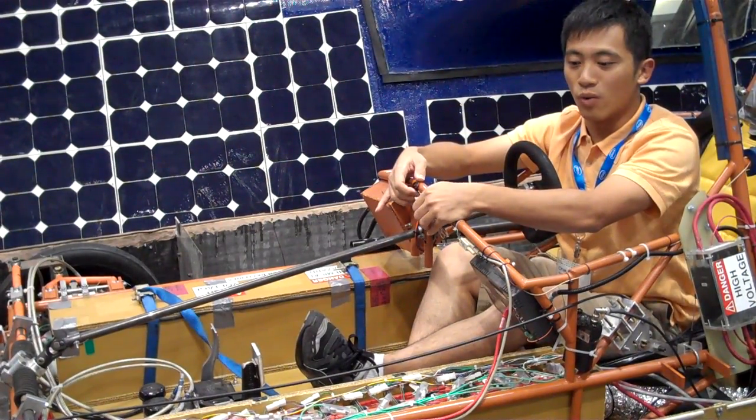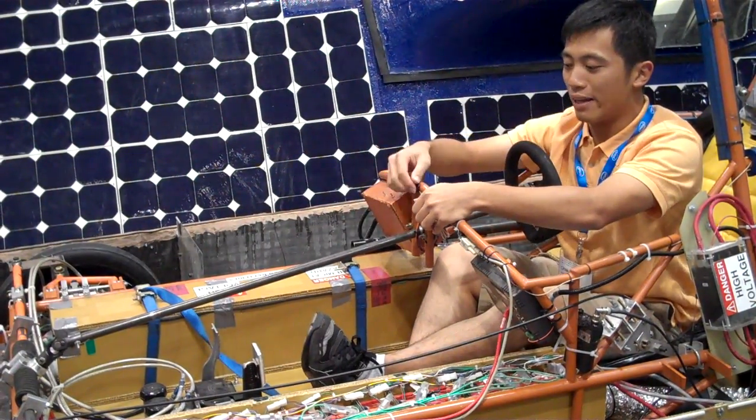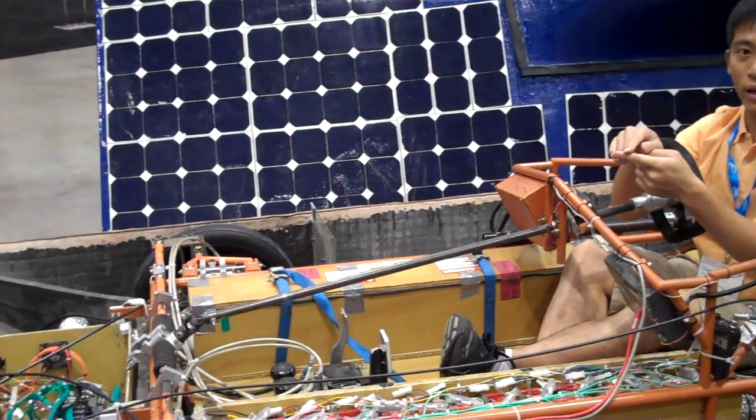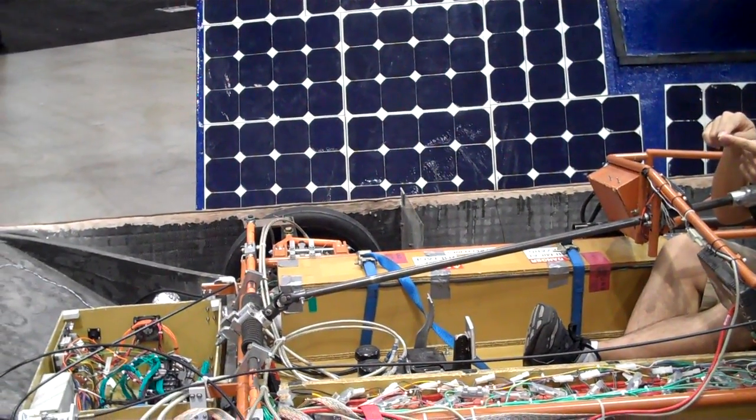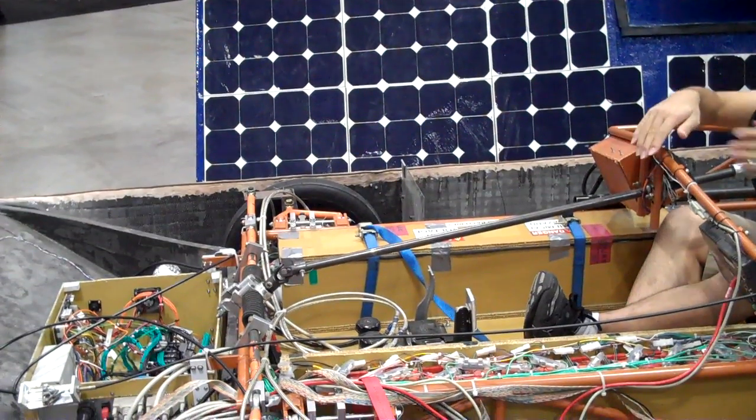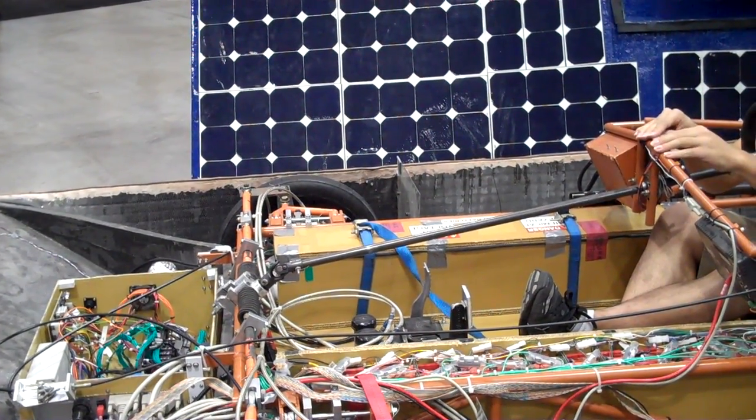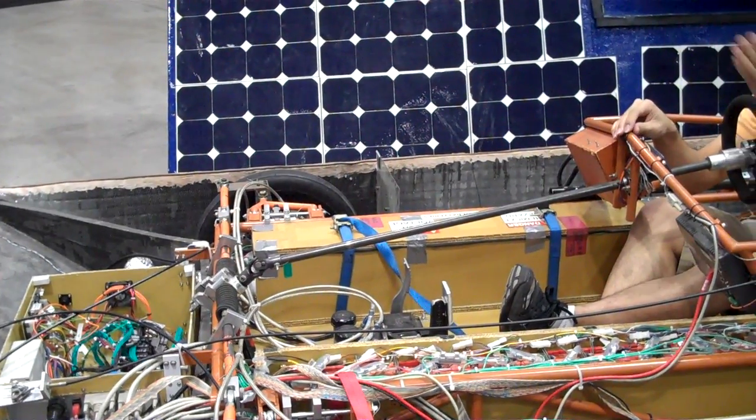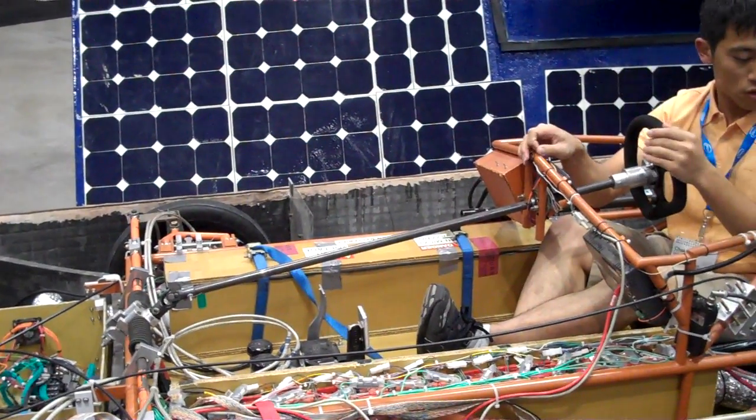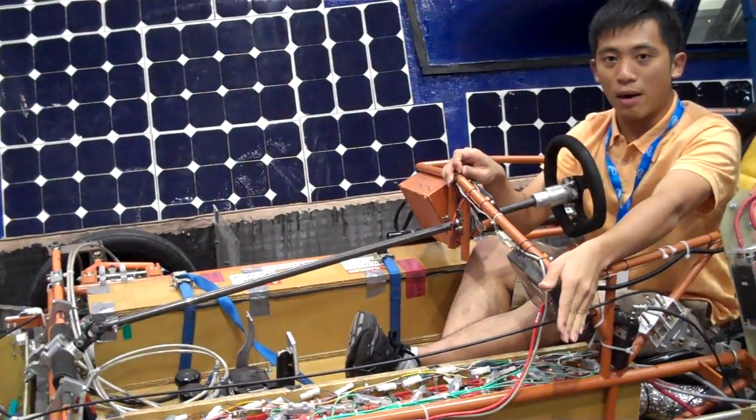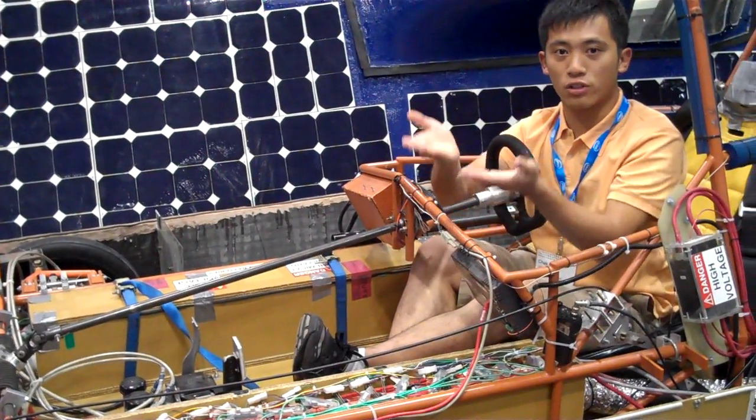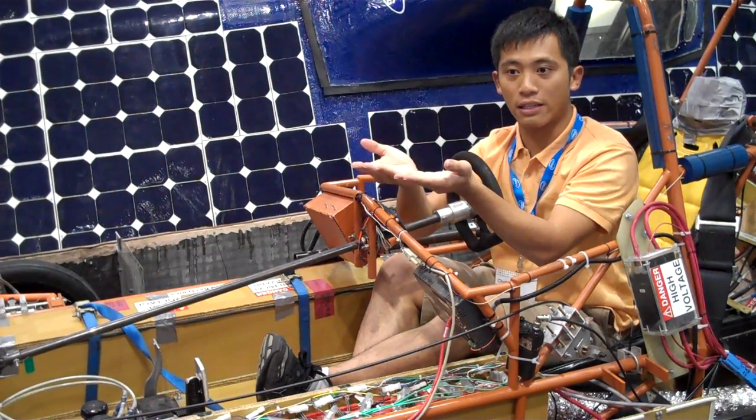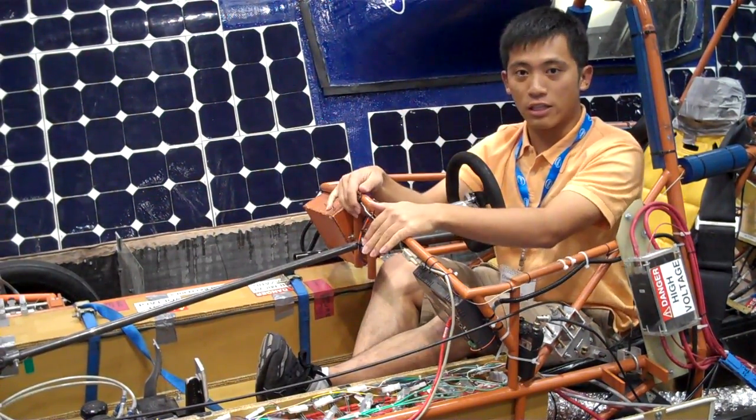And what we use in our products is we have a CompactRIO, which does battery protection to make sure the batteries do not fall outside their safe operating parameters, array control to switch on and off the three sub-arrays, and lithium-ion cell balancing to make sure the cells are in nearly the same state of charge so that we can put more energy into the battery bank.